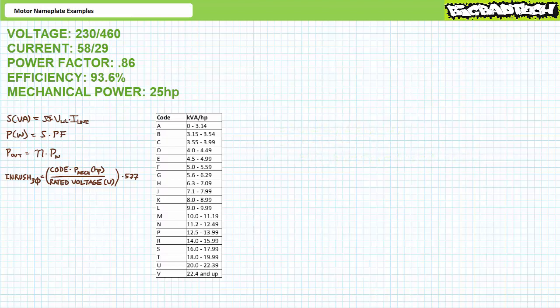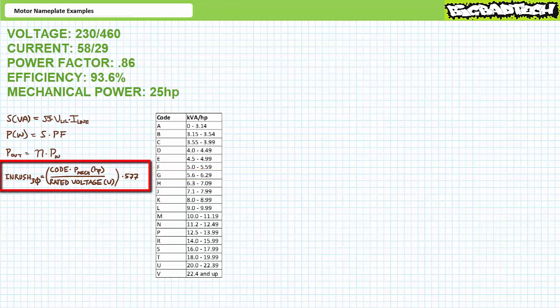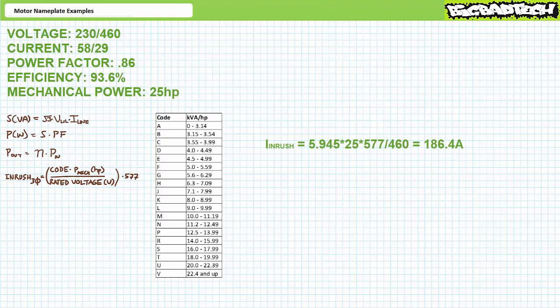Let's now calculate the inrush experienced by this motor upon closure of a direct online full voltage starter, for the high voltage configuration. An inrush code of G represents the constant 5.6 to 6.29. Aiming for center of mass, let's call it 5.945. One can estimate inrush current using the kilovolt ampere per horsepower code: inrush equals the code constant times motor horsepower divided by rated voltage times 577. Substituting these values, one would expect an inrush of 186.4 amps. Luckily, the surge doesn't last for long.